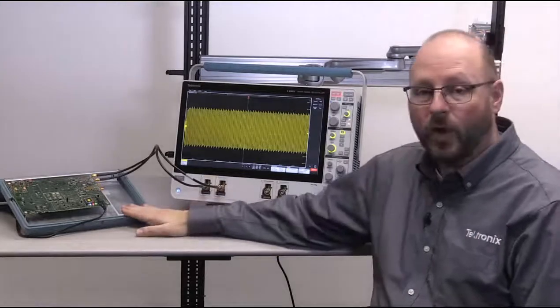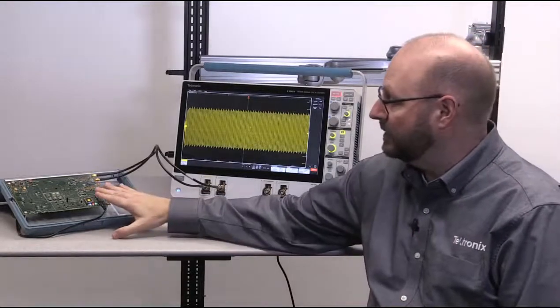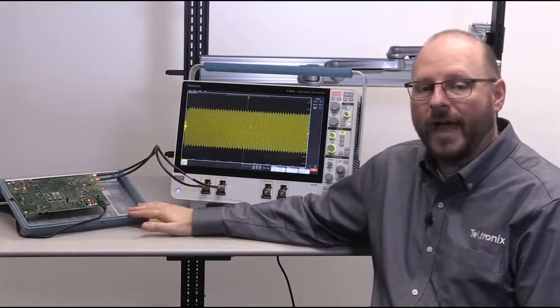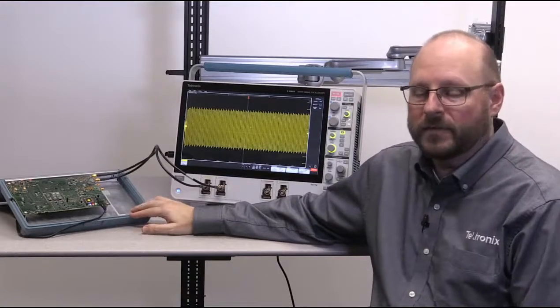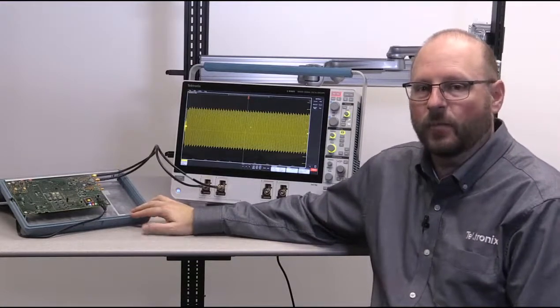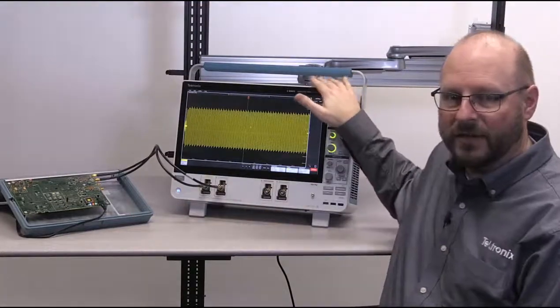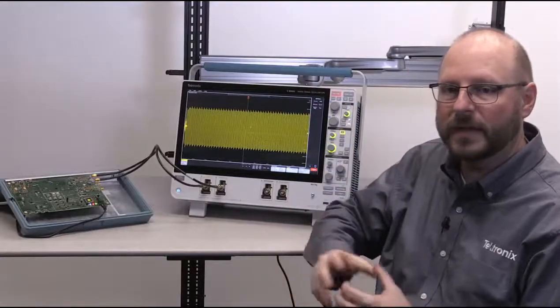I've also flipped on the power for the Training Board 3 and I've verified that the 7-segment displays both read 0, 0, which is going to output a 2.5 gigabit per second 8B10B signal that's very similar to a PCI Express Gen 1 signal. Now on the instrument itself, I'm going to take advantage of recalling a session file just to speed up the setup of the instrument.